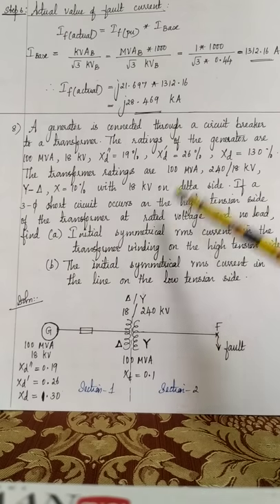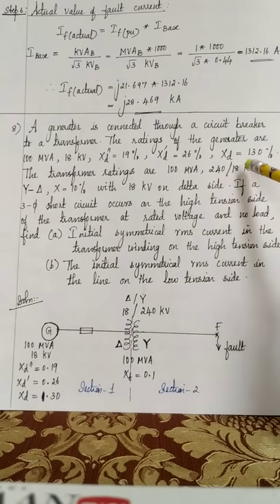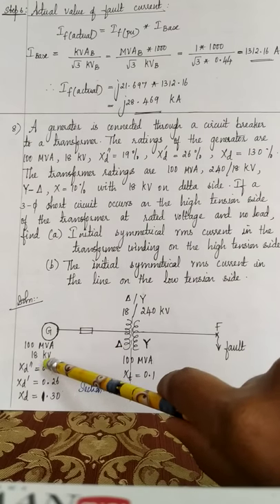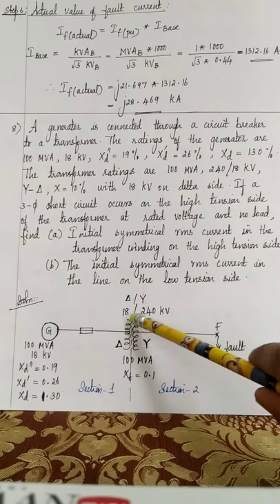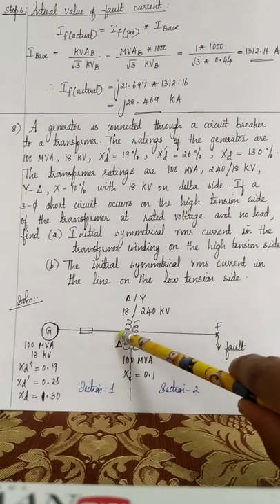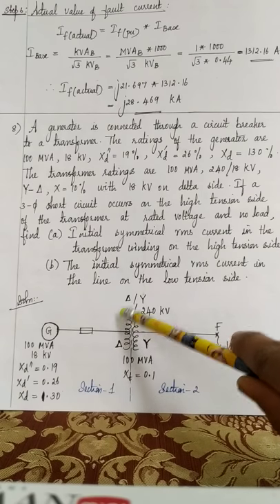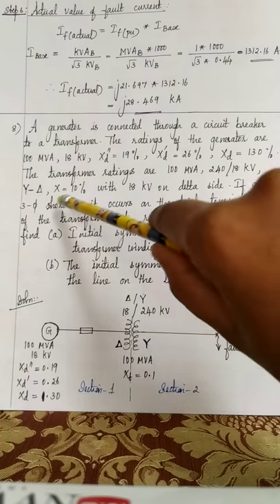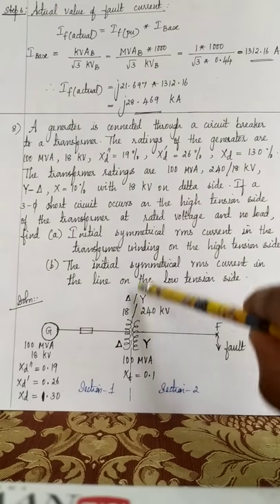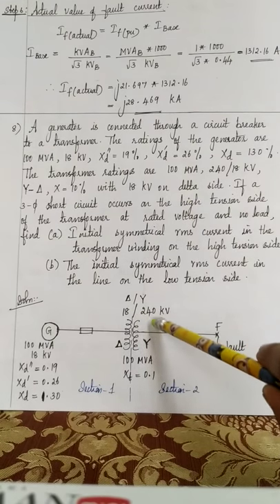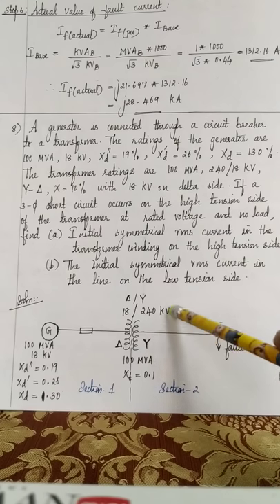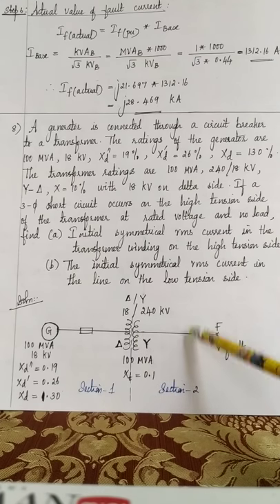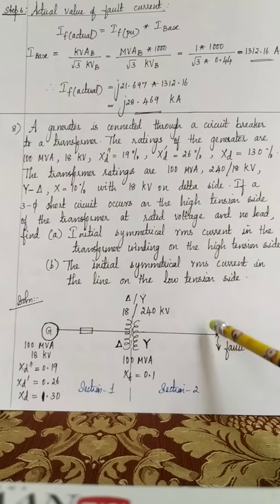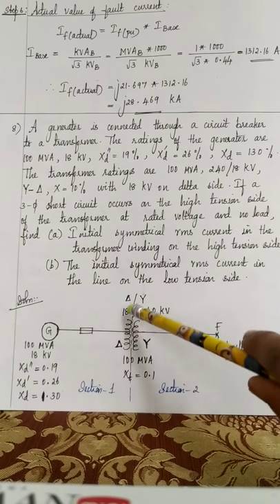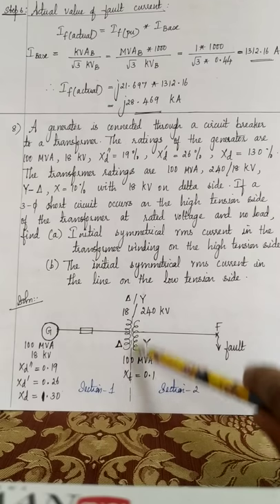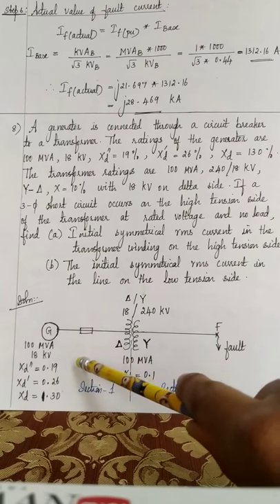So now the transformer, they had given the rating as 240 by 18, but the generator kV is 18. So it is not possible to connect as 240 by 18. So we have to reverse the transformer, 18 by 240, and 18 kV is the delta side. They had given 18 kV on the delta side and the star side is 240 kilovolt, and the 240 kilovolt side is the high tension side and the fault occurs on the high tension side. Okay. So with respect to the transformer, I have divided the power system network into two sections, section 1, section 2.